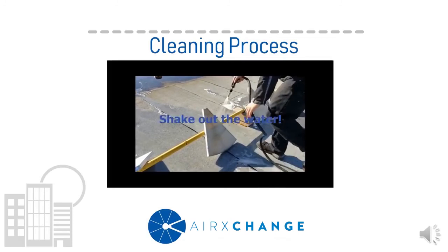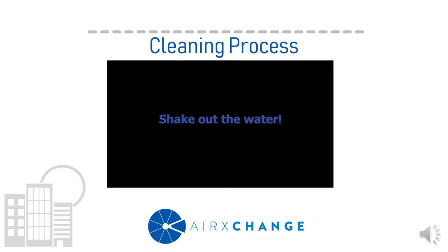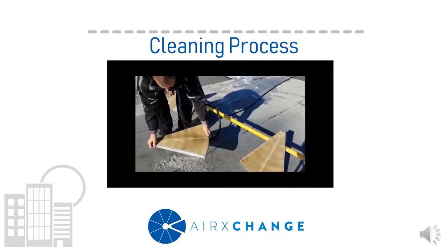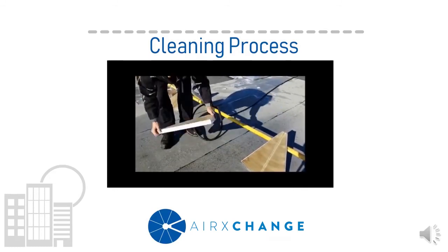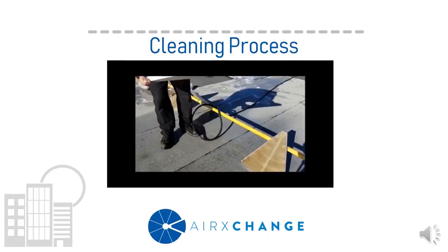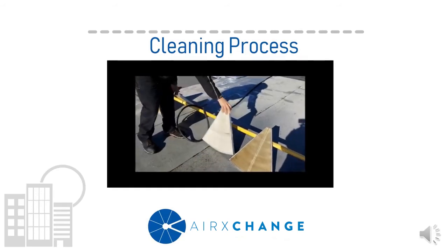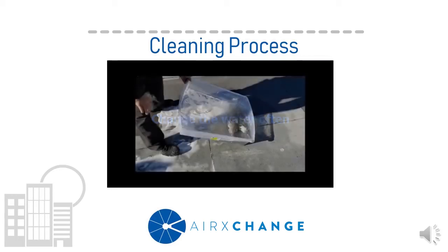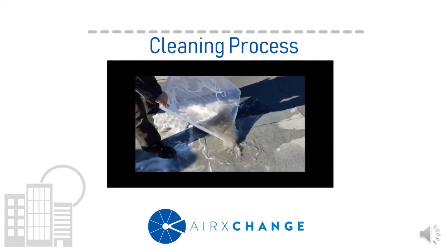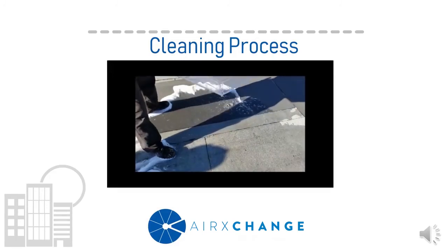And an often overlooked benefit of cleaning the energy recovery wheels this way is that it's a more hygienic and safer approach than cleaning in place, which introduces a lot of water to the cabinet or potentially dislodges debris and pushes it further downstream. Now, after shaking the majority of the water out of the segments, they really don't have to sit for that long. You can place them back into the unit, and as soon as that unit kicks on, the air is going to dry them out rather quickly.